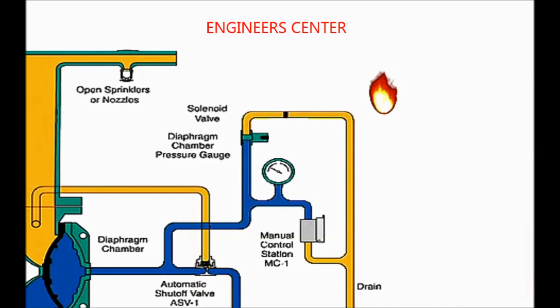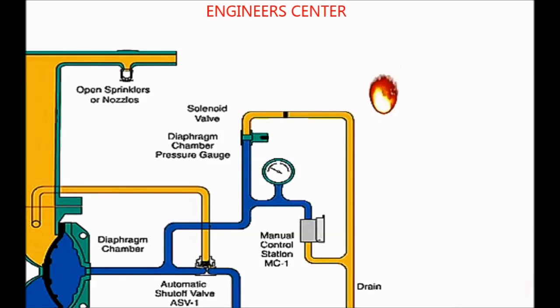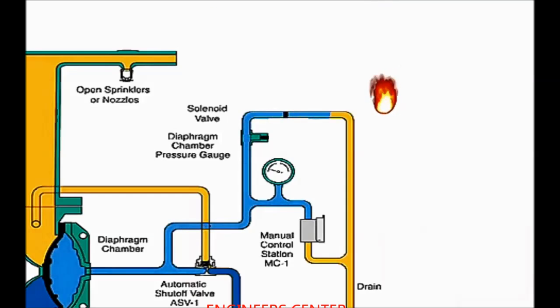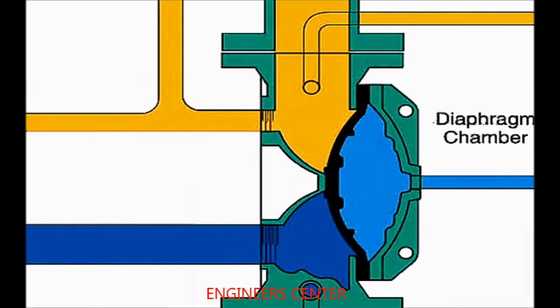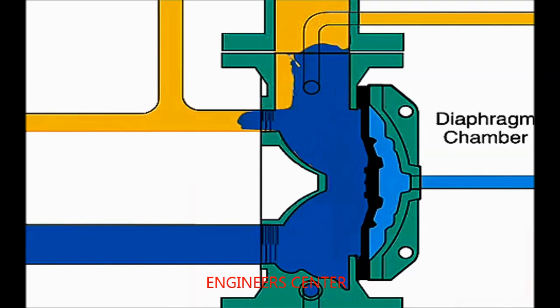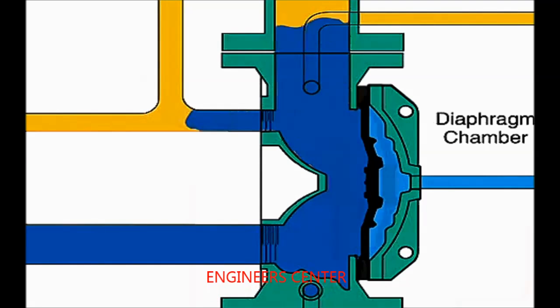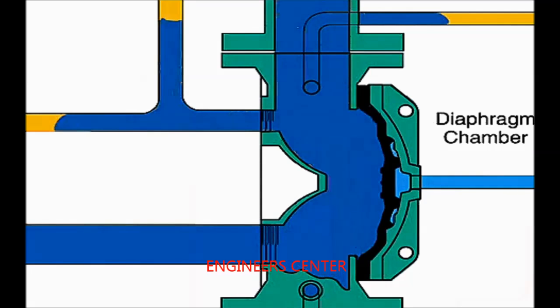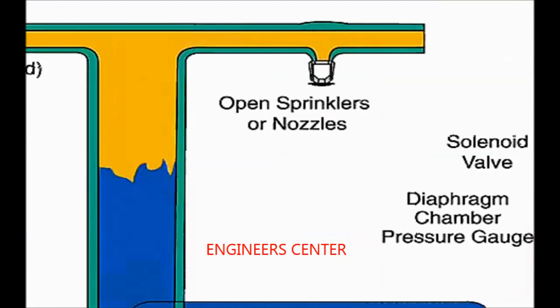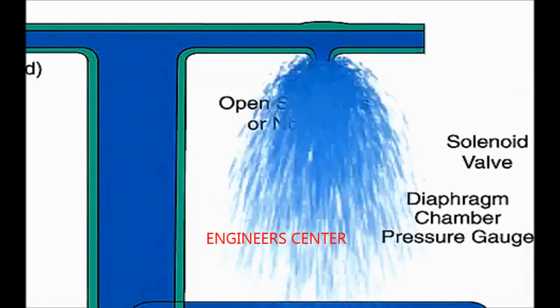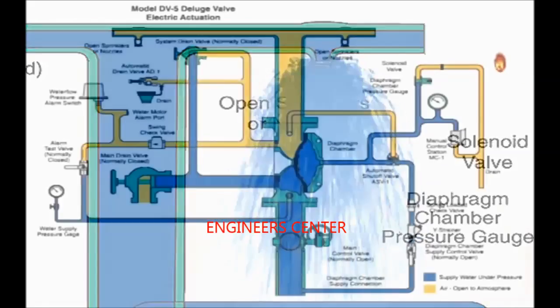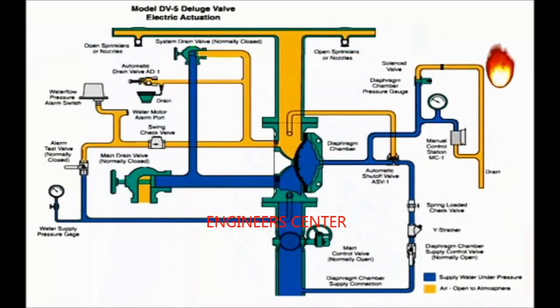In case of fire, when the operator presses the push button in the control room, it sends a signal to the solenoid valve, opening the path to the drain and consequently depressurizing the priming chamber pressure. This causes the water supply to move the diaphragm, pushing it backward to allow the water to reach the sprinklers or nozzles. Let's see the system in action.